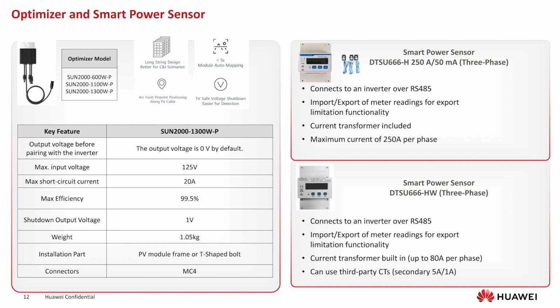So with the optimizer itself, you could have 0 volts on the roof. The max input voltage is 125 volts. The max short circuit current is 20 amps. The max efficiency is 99.5%. Shutdown output voltage is 1 volt. It weighs 1 kilogram. It's got MC4 connectors, okay?